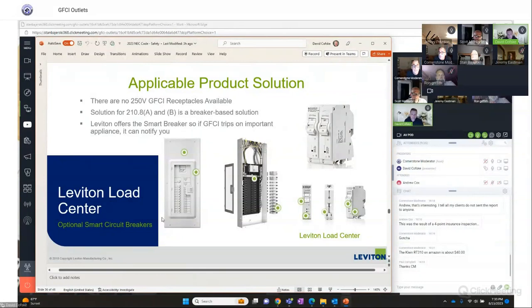Now I'm going to kind of slide into the load centers, and we got into this business back in 2018. The reason why was the GFCI receptacles, which have been around for a long time. Leviton had started to see sales decline on GFCI receptacles because when you were building a new house or somebody was making an upgrade, they chose rather to protect those circuits from the load center, from the panel, instead of from devices, receptacles in the wall. So we entered this market back in 2018.